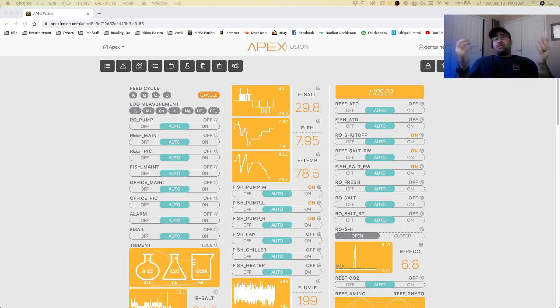Yeah, Brian, that's the right thing to do. I tell everybody leak sensors are tremendous investments. I think optical sensors too. I don't like float switches. I think float switches fail. I've had better success with optical sensors. I know people that say they have problems with optical sensors.